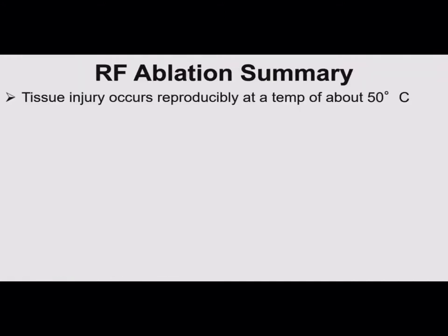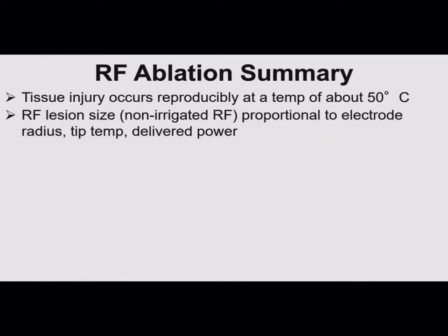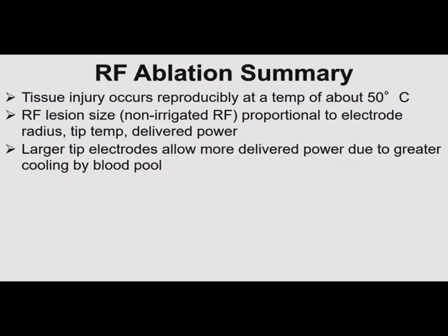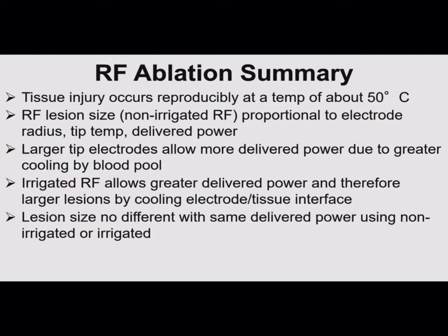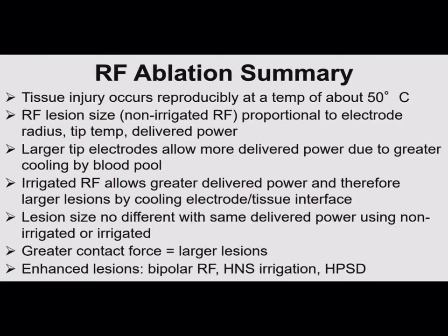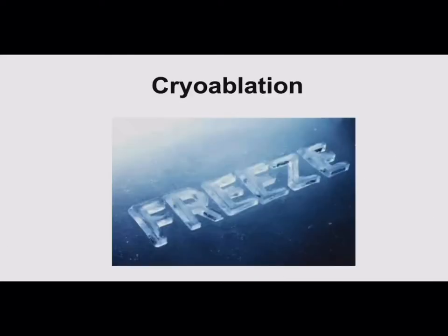RF summary: tissue injury occurs reproducibly at about 50 degrees. With non-irrigated ablation, RF lesion size is proportional to electrode radius, tip temperature, and delivered power. Larger tip electrodes allow more delivered power due to greater cooling by the blood pool, but you need to give more power. Irrigated RF allows greater delivered power and therefore larger lesions by cooling at the electrode-tissue interface — but lesion size is no different with the same delivered power using non-irrigated or irrigated RF. Greater contact force generally gives larger lesions. If you're struggling with a deep substrate: bipolar RF, half-normal saline irrigation, or high-power short-duration lesions are options.